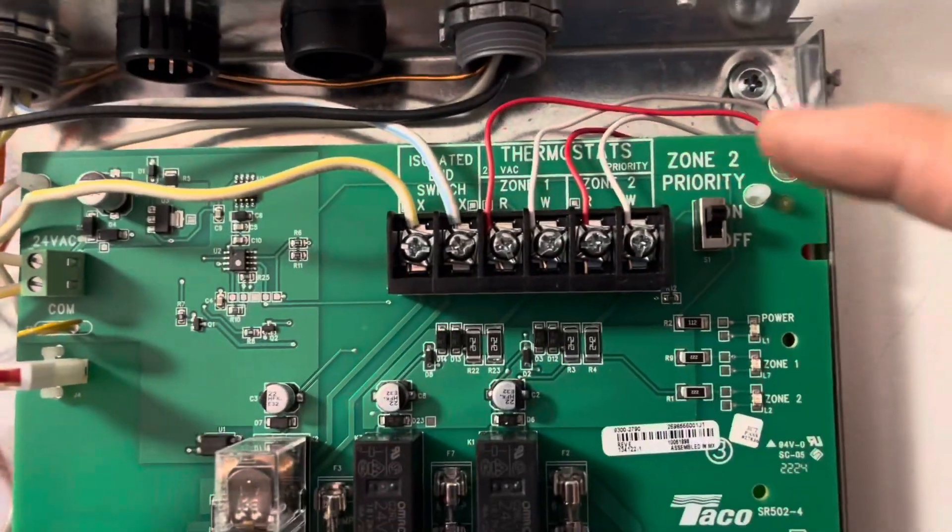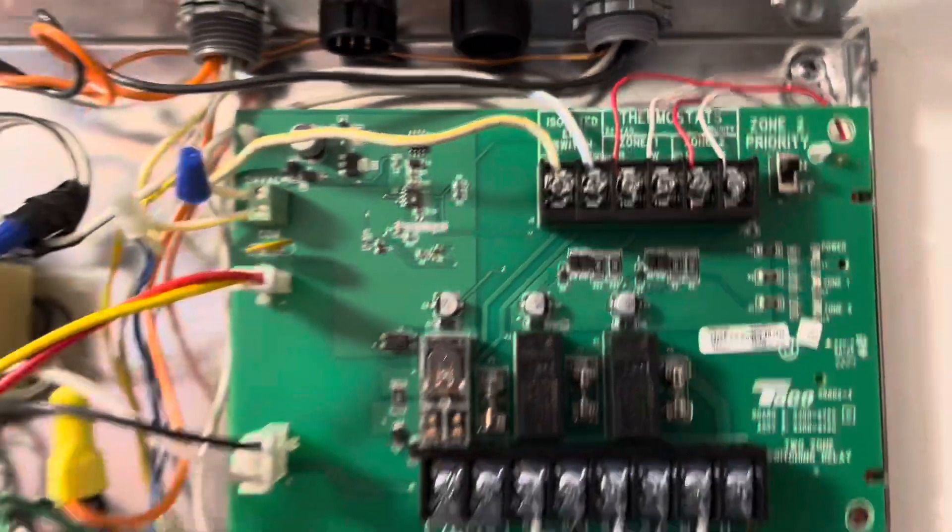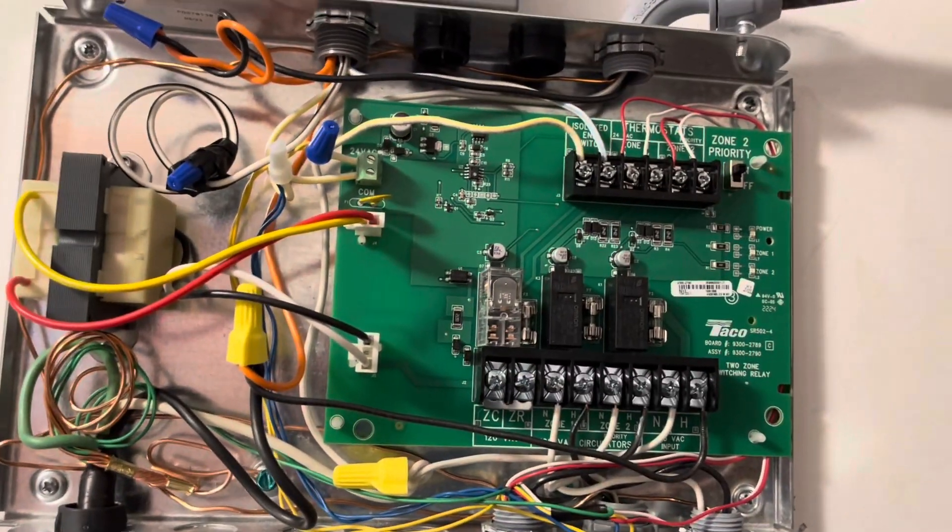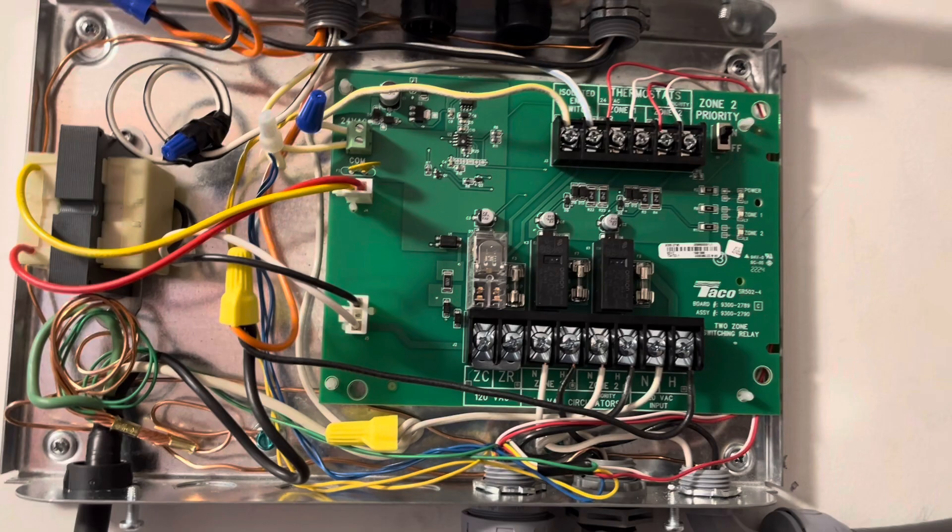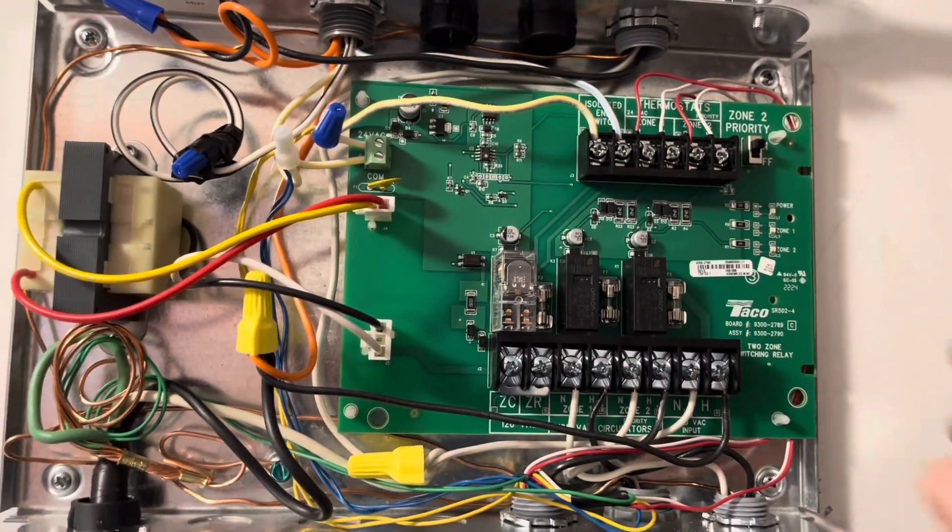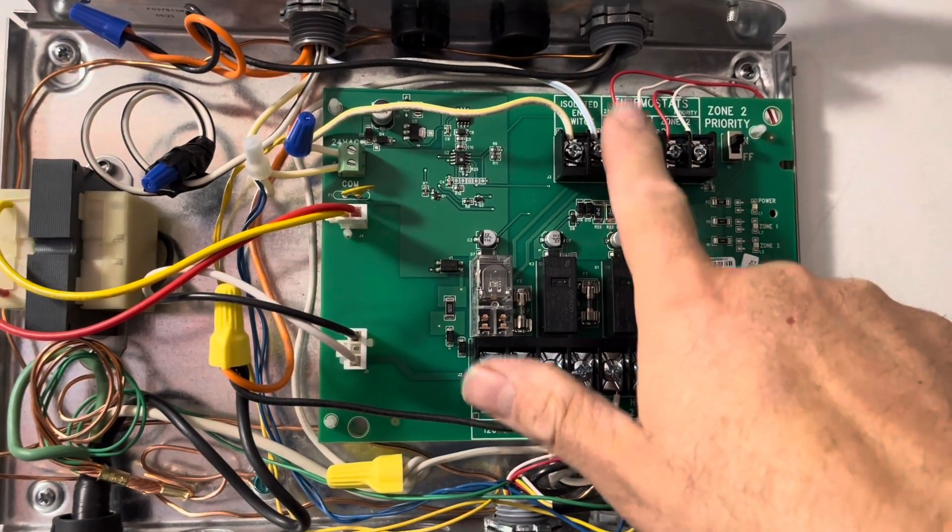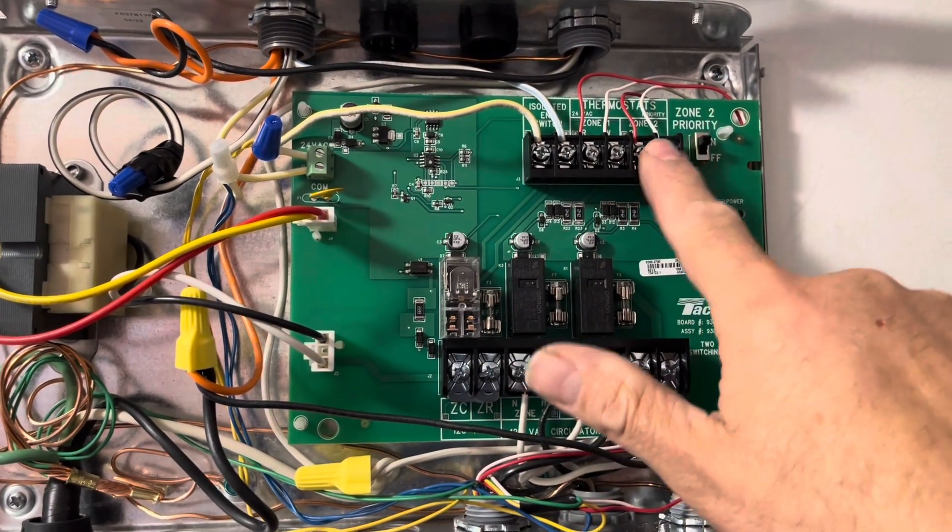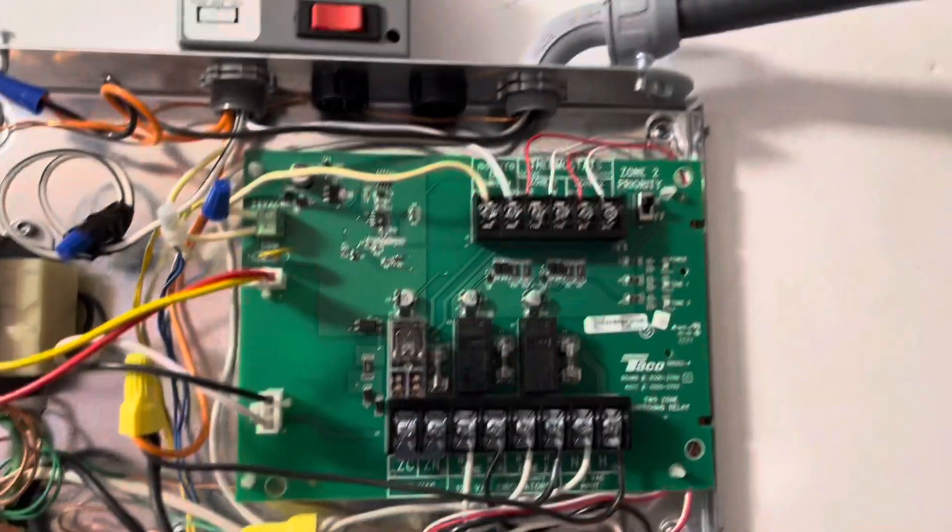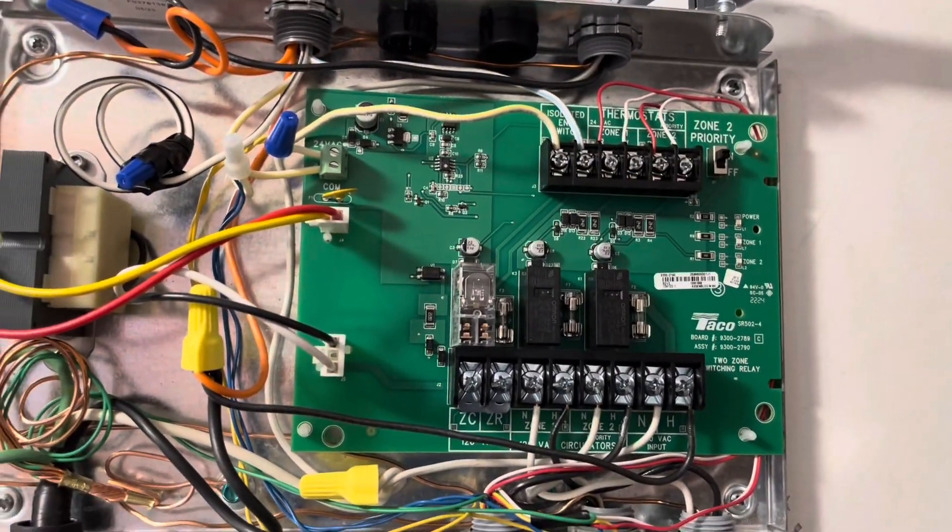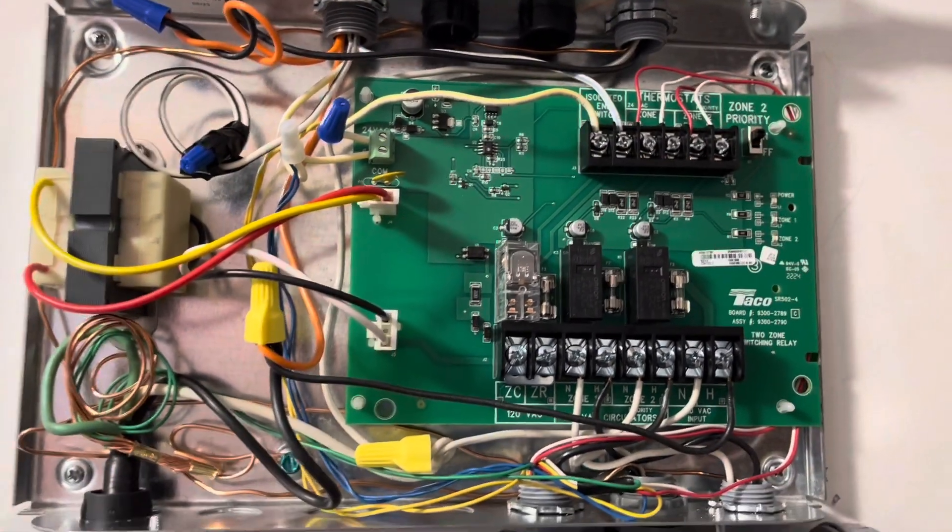This is a primary zone two priority. And what that means is if both zone one and zone two call for heat at the same time, the system will keep zone one off and give priority to zone two until zone two comes to its heat. And then it will allow zone one to come on.